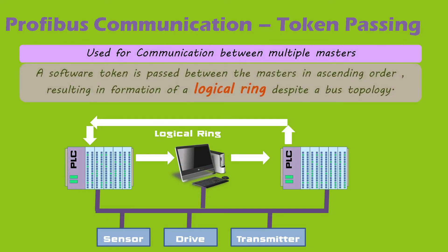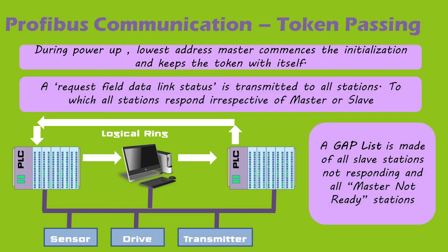The token passing mechanism is used for communication between multiple masters on the bus. A software token is passed between masters in ascending order. Although the physical topology is a bus, the sequential token passing creates a logical ring between the masters. During power-up, the master with the lowest station address commences initialization and keeps the token. It then transmits a request for data link status to each station in increasing address order, and the token is passed to the first master station that responds. Slave stations and non-ready masters are recorded in an address list called the gap list.